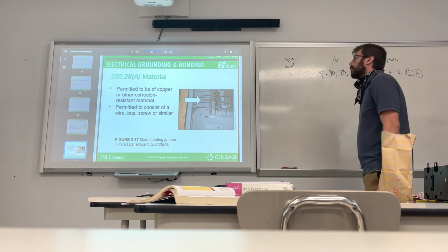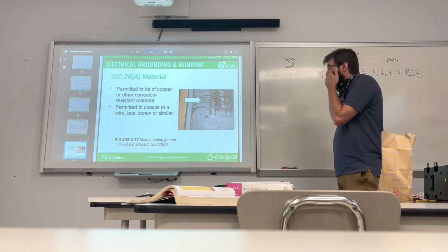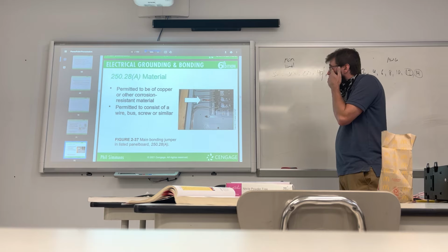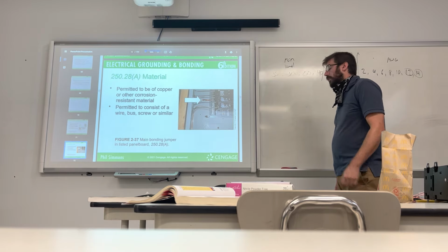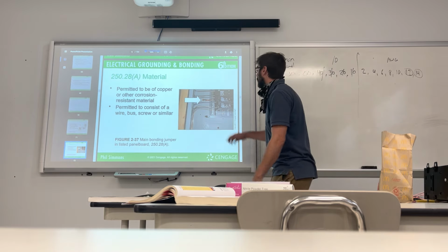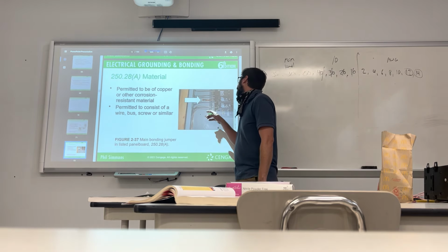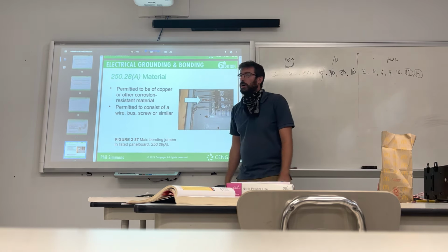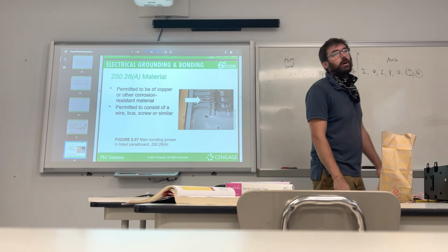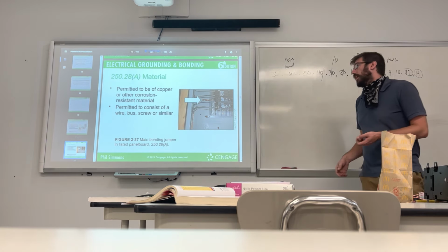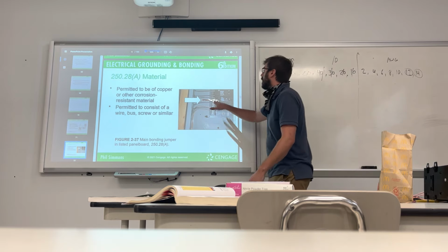Material. Permitted to be of copper or other corrosion-resistant material. Permitted to consist of a wire, bus, screw, or similar. Yeah, this is the bonding jumper. This is the neutral bar, and that's bonding that neutral bar to the panel, right? There could be a couple of different methods.